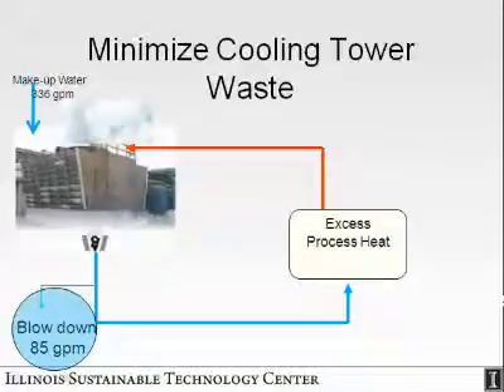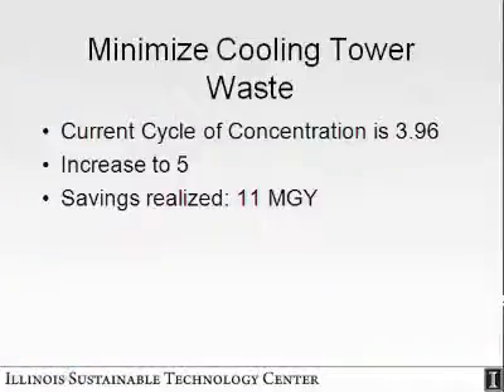But this cooling tower also is susceptible to scaling by salts or by bacteria and stuff like that. So to make sure this cooling tower operates efficiently, we will have to waste a certain amount of water that's called a blow down. And that, in this particular instance, was about 85 gallons per minute. So the question is, can we reduce this amount of blowdown that is being currently wasted? And the answer turns out to be yes. So I won't bore you with the details of what it means, but essentially you can operate the cooling tower more efficiently, and if you did that, you would save another 11 million gallons per year.